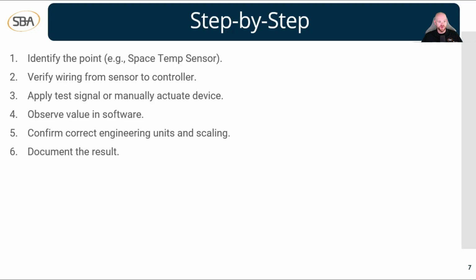So to start off here, we're going to identify our point. Example for this is going to be a space temperature sensor, so like a wall-mounted zone sensor. Next thing, we've got our point figured out. So the next thing we're going to do is verify our wiring from the sensor to the controller. We do this with a multimeter, and we can either disconnect the wire and then bounce the wire together to get an audible beep to tell us that there's continuity through the wire and that it is working, or we can go to our software and we can verify the wiring physically and then go to our software and make sure that we're communicating with our controller.